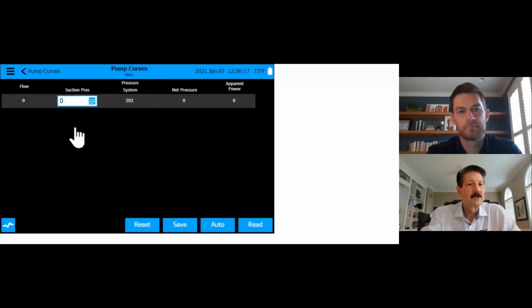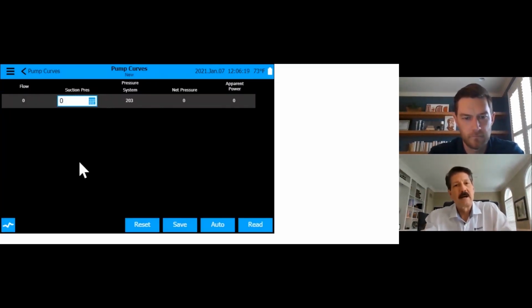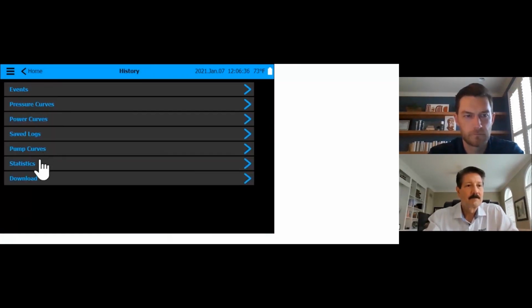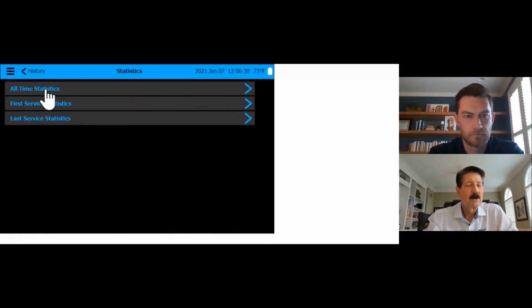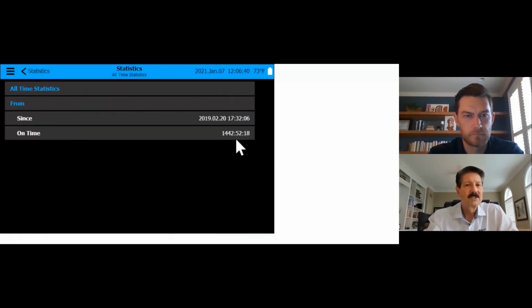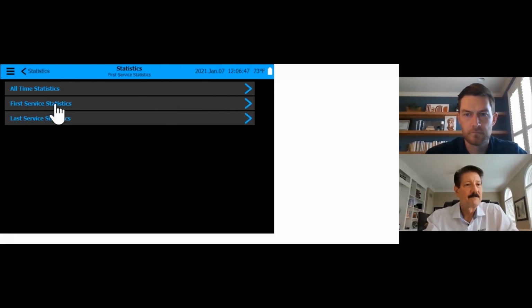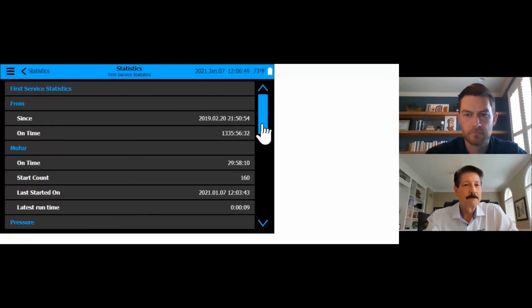Pump curves, we can actually do manual pump curves. I won't get into too much of this, but we can do automatic with a digital flow meter that's available in the market now that sends us a 4 to 20 milliamp signal or 0 to 10 volt. We can do that. Statistics, all-time statistics. This is actually when it was commissioned and how much time we have on this, obviously. First statistics. Okay, here we go.